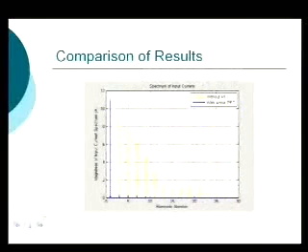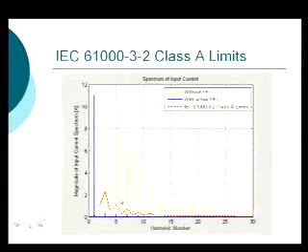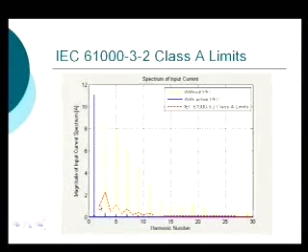Let's compare the spectrum of both results. Basically, the fundamental is approximately the same, but you can see how many more harmonics are present without power factor correction, and how good a job the power factor correction does. Comparing to the IEC limits — it looks a little jagged because there are lower limits on even-order harmonics, but we don't have any — the converter with active power factor correction meets the IEC limits, whereas the one without fails.